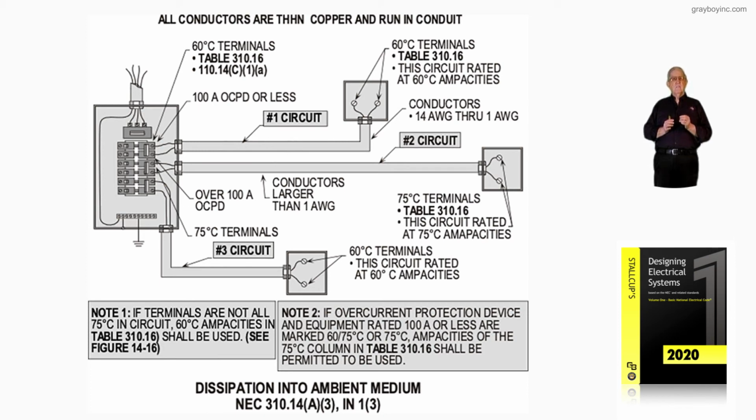The devices say they're rated 75 degrees C, but we have a 60 degrees C termination for the equipment.